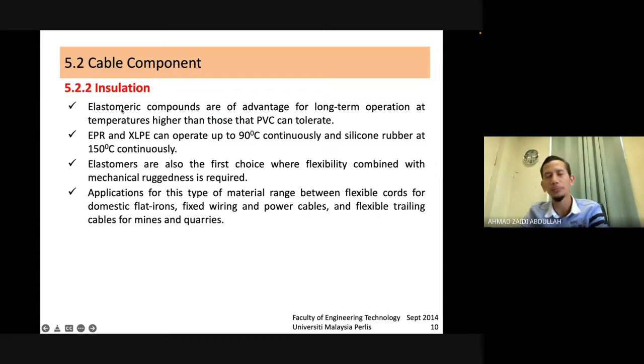elastomeric compound. Okay, so for XLPE, it can be operated up to 90 degrees continuously, and silicon rubber at 150 continuously. So that's why for underground, because we know that for underground and for the high load capacity, we use the insulation type of XLPE because it can withstand for a long time with the higher temperature. So elastomer are also the first choice where flexibility combined with mechanical ruggedness is required.